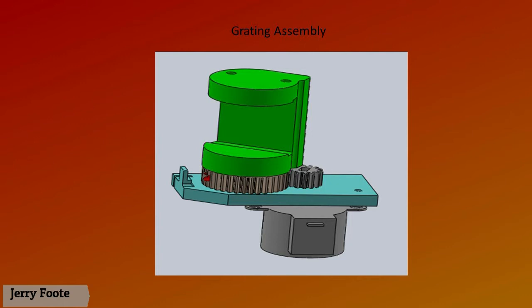Another issue we have found is with collimation. If the collimation is not spot on, you're going to have difficulty with a decreased resolution. The reason is, if the collimation is off, then you have either a diverging beam or a converging beam approaching the grating. This means that the alpha angle on the incoming beam on one side is different than the alpha angle of the beam coming in on the other side of the grating.